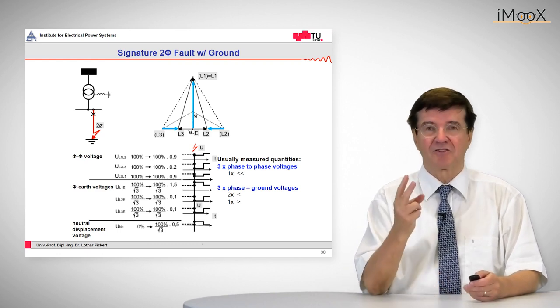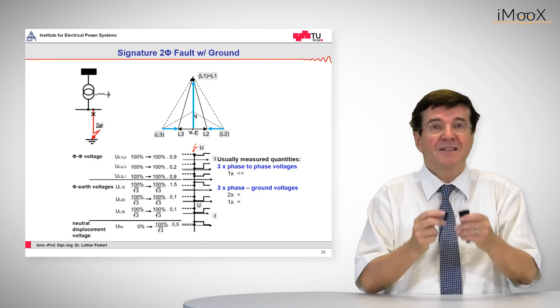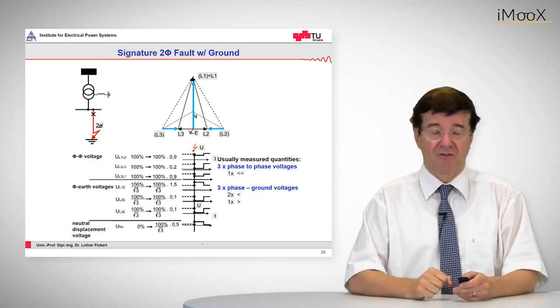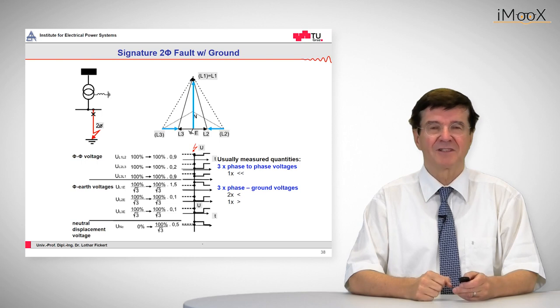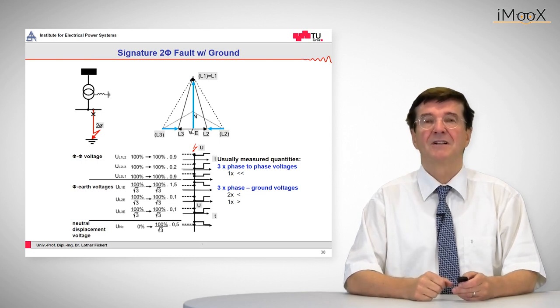And when it comes to the phase-to-ground voltages, we can see that two phases collapse versus ground and, amazingly enough, the third voltage goes up. So this is very characteristic for this type of fault where ground is involved.